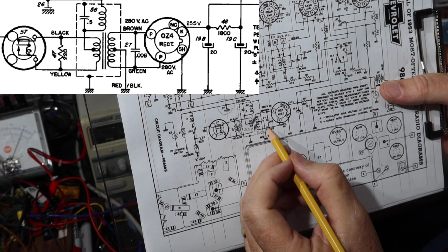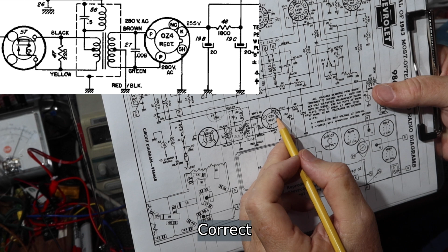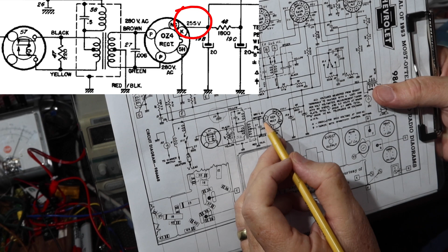If I do, then we'll start to see something happening in the transformer. We'll see that come out where I've got this hooked up to measure voltage on either side of that capacitor, which gives us voltage across the full winding. We're going for this target voltage here, which is about 280 volts. I'm assuming that may be to ground, so it could be double that from here to here. If we get that, then maybe we'll put in the rectifier and see if we get this out. But this will be AC, so we'll check that first.